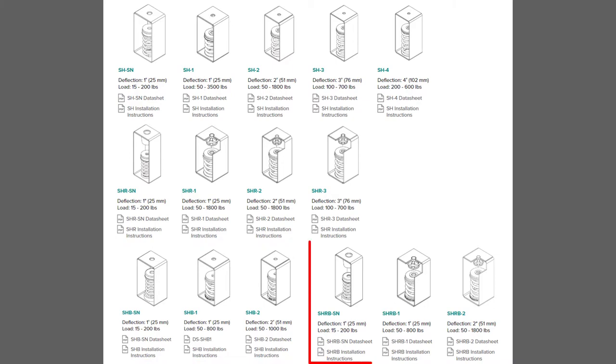The last group shown here is a combination of all three. These have springs, rubber elements, and rubber cups. Typically these are provided where specifically required by project documents. They provide the highest degree of protection from the widest range of frequencies and from short-circuiting caused by misaligned hanger rods.